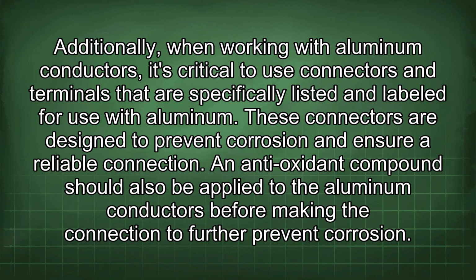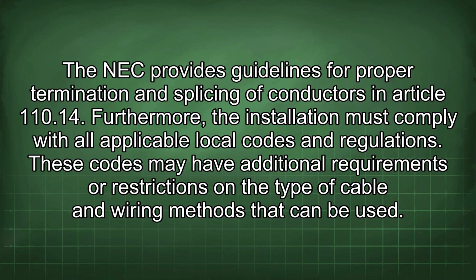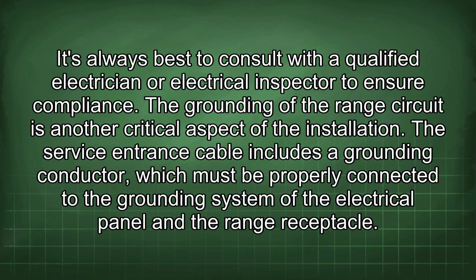Additionally, when working with aluminum conductors, it's critical to use connectors and terminals that are specifically listed and labeled for use with aluminum. These connectors are designed to prevent corrosion and ensure a reliable connection. An antioxidant compound should also be applied to the aluminum conductors before making the connection to further prevent corrosion. The NEC provides guidelines for proper termination and splicing of conductors in Section 110.14. Furthermore, the installation must comply with all applicable local codes and regulations. These codes may have additional requirements or restrictions on the type of cable and wiring methods that can be used. It's always best to consult with a qualified electrician or electrical inspector to ensure compliance.